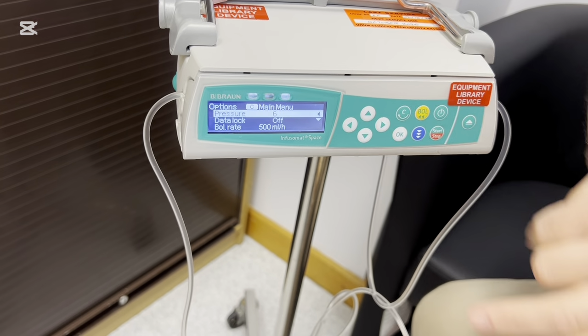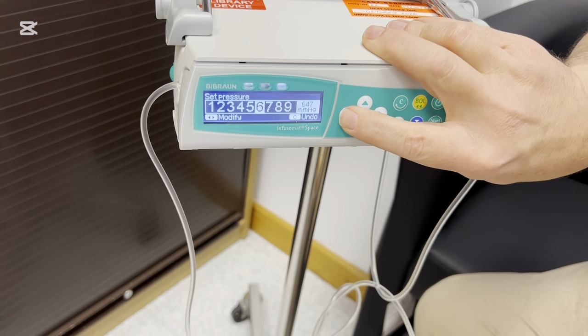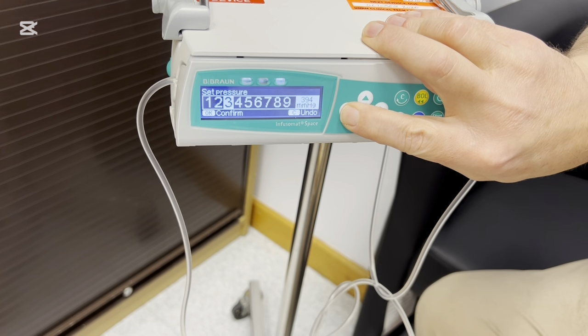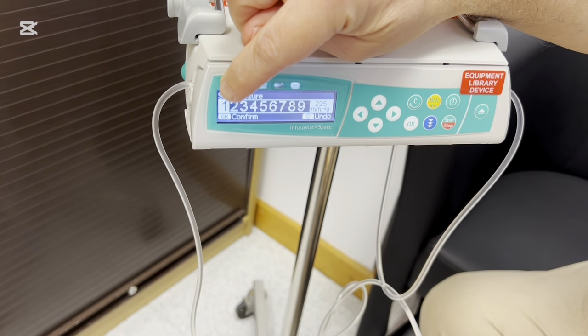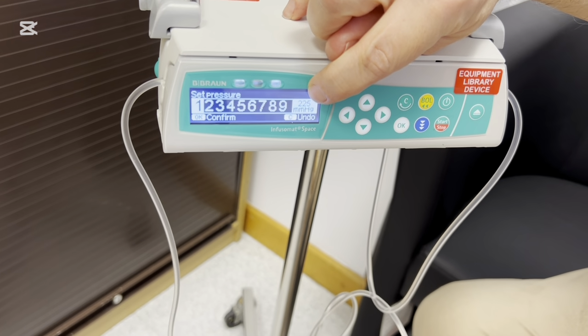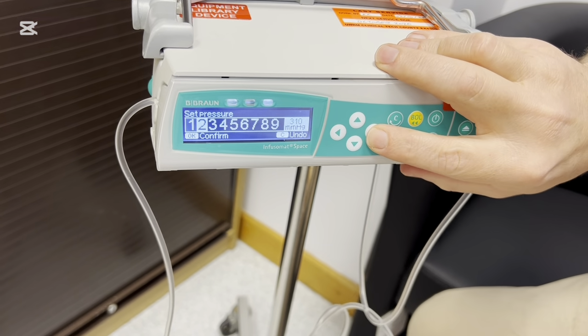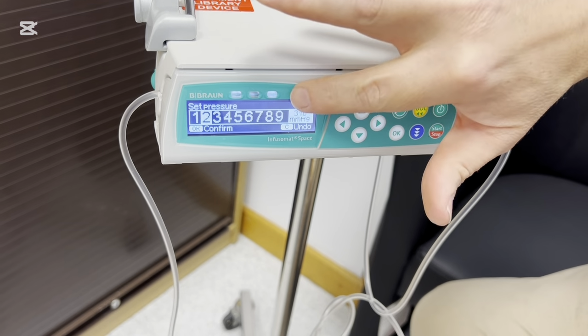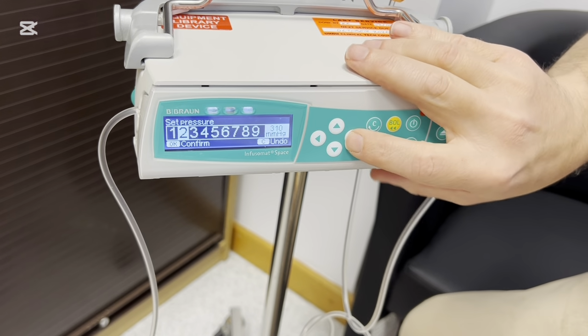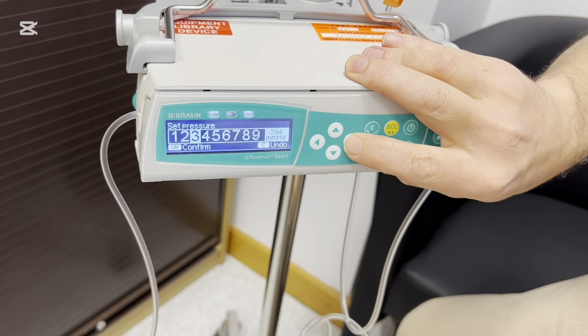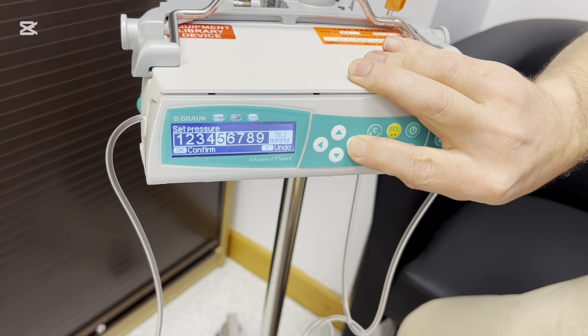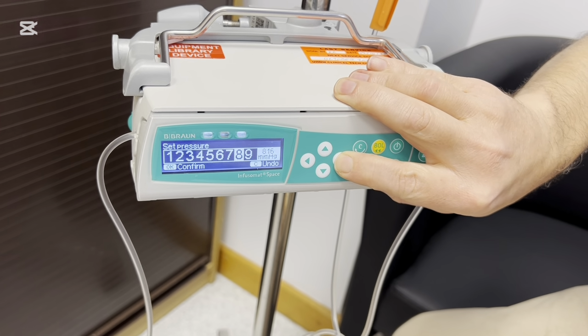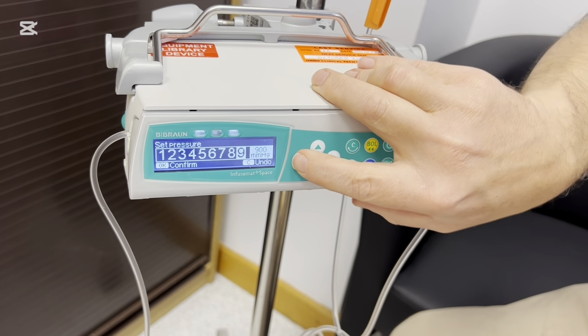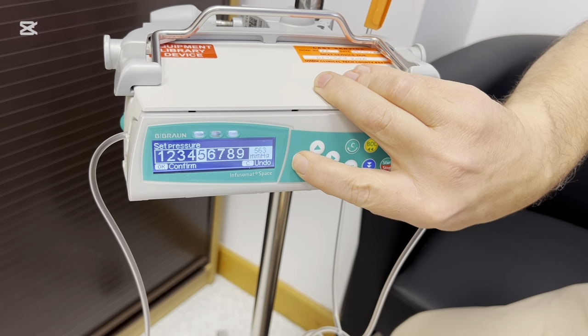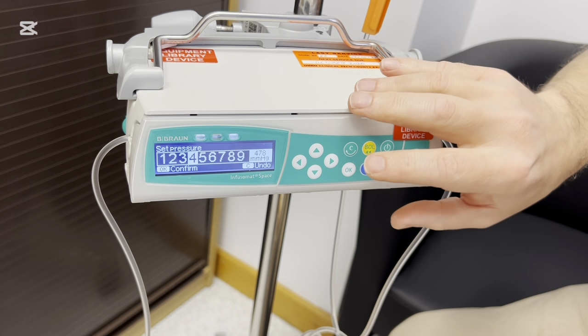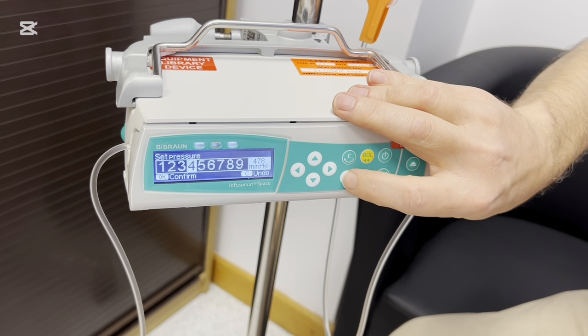So here you are, pressure. You can enter into that menu. So pumping pressure 1 corresponds to 225 millimeters of mercury, and as you sequentially go up through these numbers, you get a higher pumping pressure that it will allow you to pump against. All the way up to 900 millimeters of mercury. And 4 should be a reasonable compromise number to select.